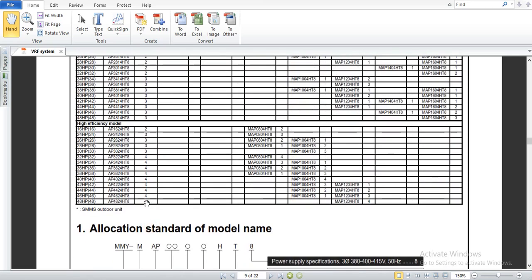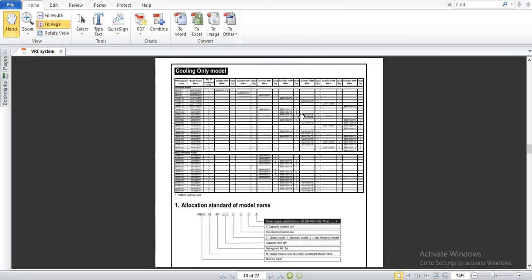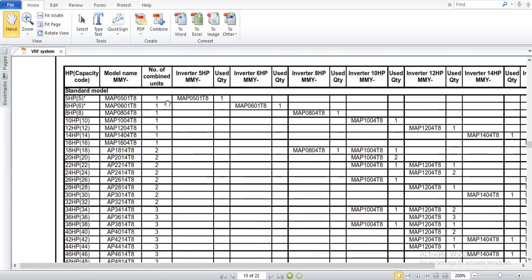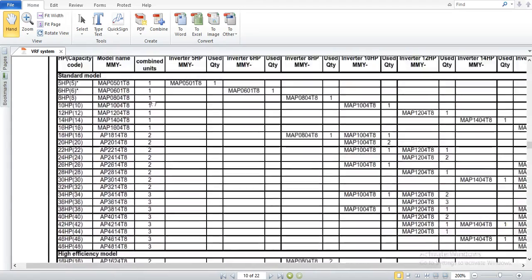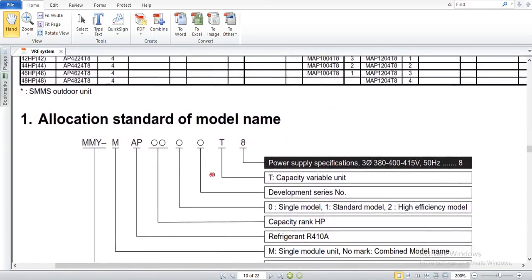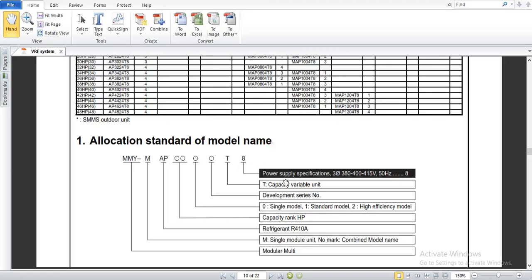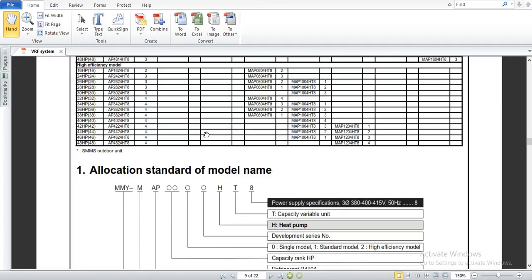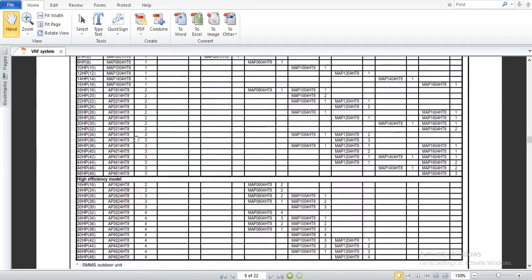The maximum number of combined outdoor units is 4, so a 48 horsepower system has 4 outdoor units. For the cooling only models, you can see the capacity code, model name, and number of combined units — standard efficiency and high efficiency. The nomenclature is the same as heat pumps, with the only difference being there is no H, because H stands for heat pump. These are cooling only models, so no H appears, whereas all heat pump models include H in their designation.